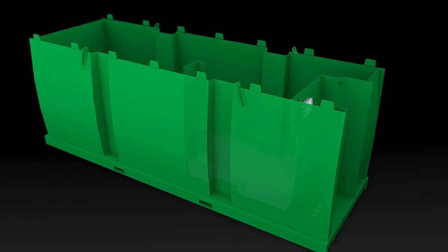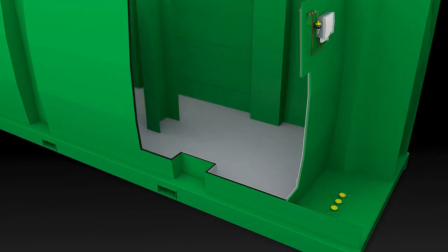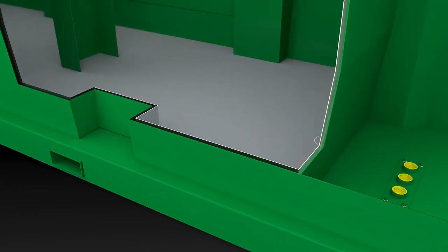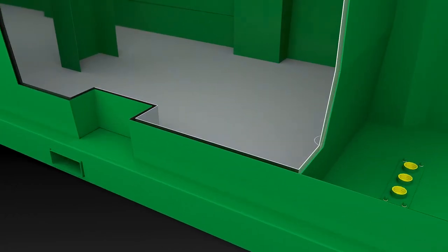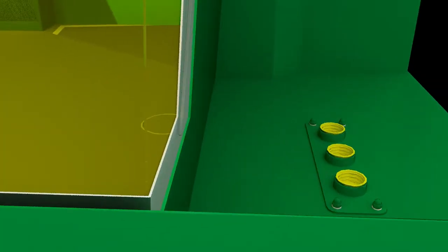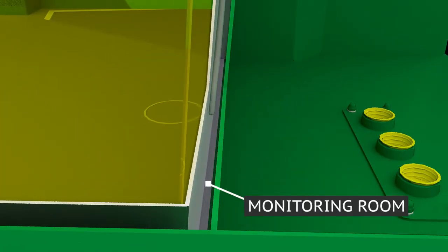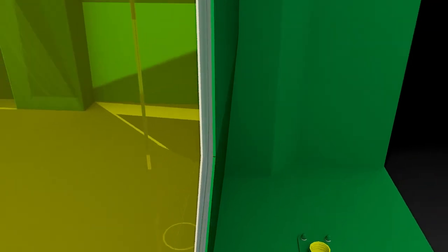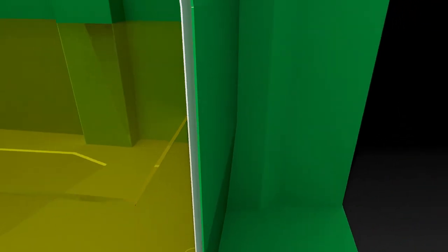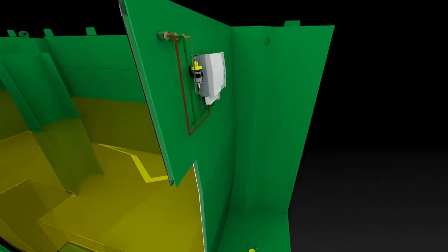The tanks are constructed with a double wall. A second wall, a second tank filled with the fluid, is welded behind the outer wall at a small distance inside. This creates a monitoring room between inner and outer wall, which is controlled by the leak detector.